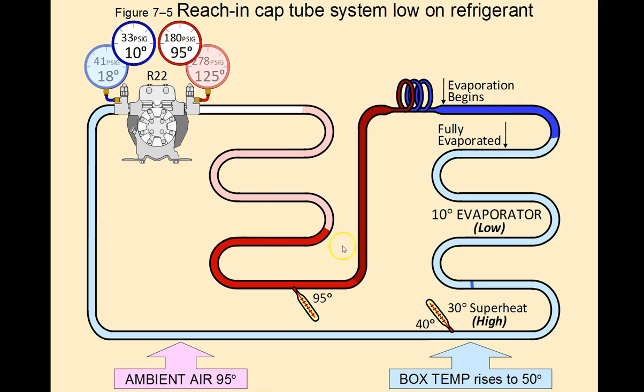On the other side of the system, now that we have low pressure because of the lack of refrigerant, the pressure drops on the high side of the system as well. Because of that lowered high side pressure, the condenser temperature is 95 degrees Fahrenheit and the outdoor ambient air temperature is also 95 degrees Fahrenheit. So it's not going to reject any heat whatsoever. It's not going to have any sub-cooling, because the ambient temperature and the condenser temperature are the same. Therefore, you're going to have very, very low sub-cooling and very, very high superheat, with both the high side and low side pressures being low.